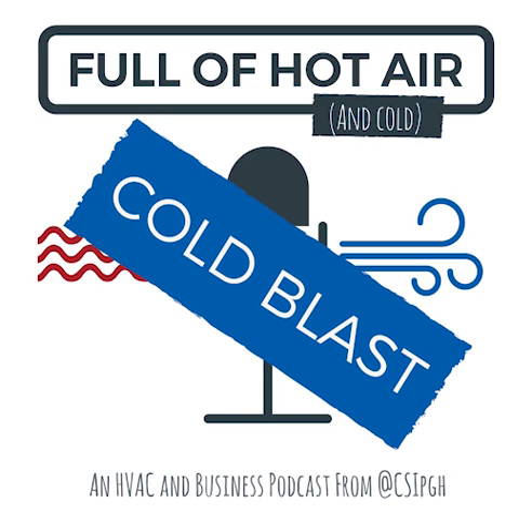How we turn watts into BTUs, anybody can do this at home, you don't even have to be a tech. If you want to know what your little electric heater is putting out, take the watts off of any electrical piece of equipment and multiply them by 3.413. That's a fixed number, and when you take the watts times 3.413, it gives you the BTUs. In this case the BTUs are 49,147. So now we have our BTUs.